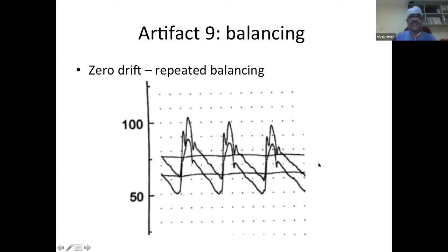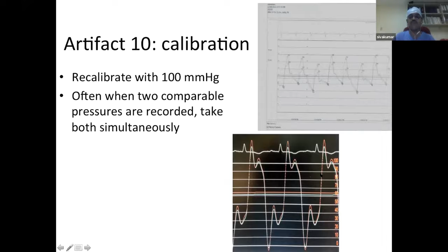Calibration error: if the calibration to 100 or 200 millimeters of mercury is wrong, with the same vessel connected to two transducers, one will show much higher pressure and the other much lower. This calibration error must be corrected by recalibrating the machine. After recalibration, the left ventricle and right ventricle pressures in the two transducers are more or less matching. This is called calibration error.